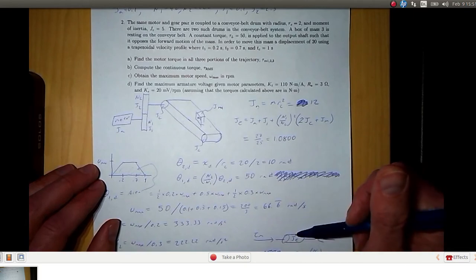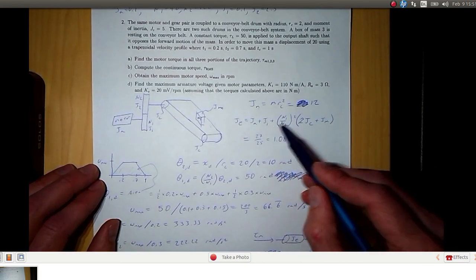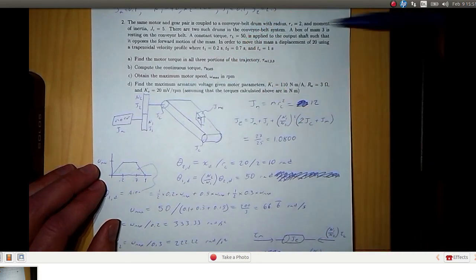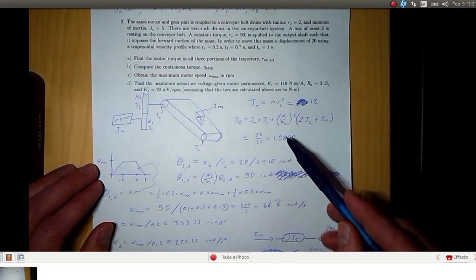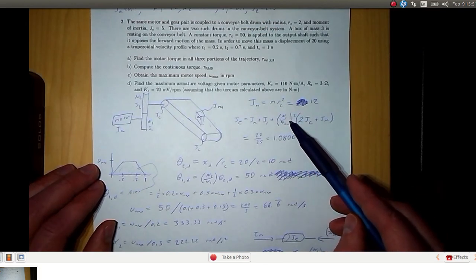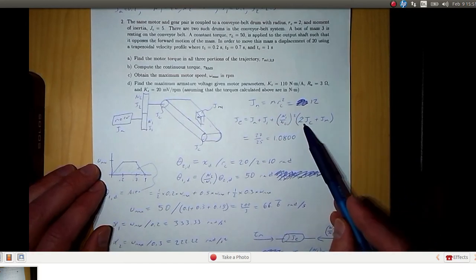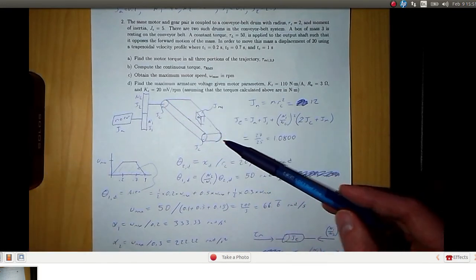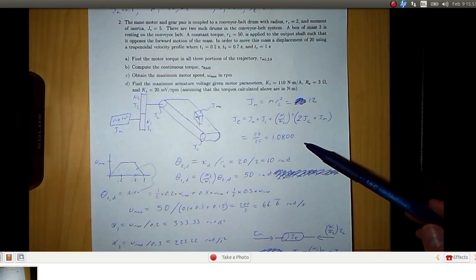And then the equivalent moment of inertia that the motor sees is just j_m plus j_1 plus the reflected moments of inertia from this drum, this drum, and the mass. So that's n_1 over n_2 squared, so the number of teeth on the destination shaft divided by the number of teeth on the source shaft, that quotient squared, and then the moments of inertia on the source shaft, which is 2 times j_c plus j_m. And that works out to be 1.08.